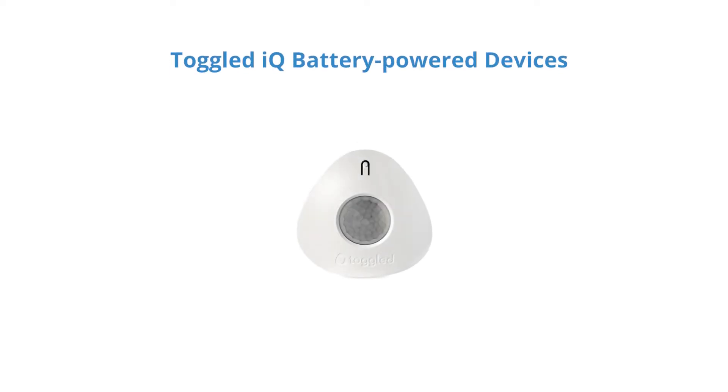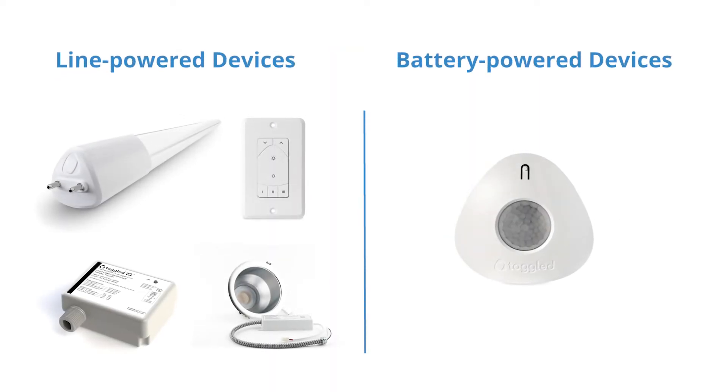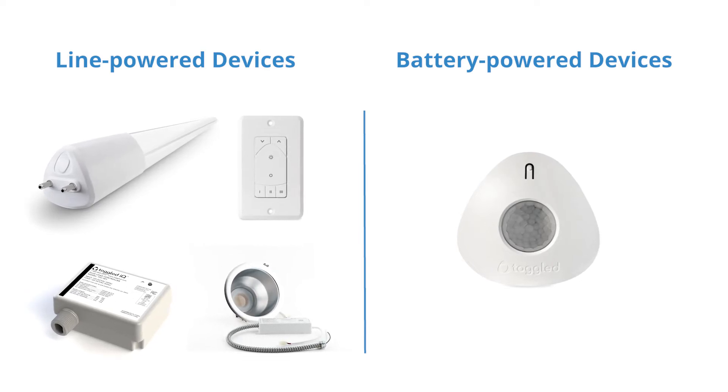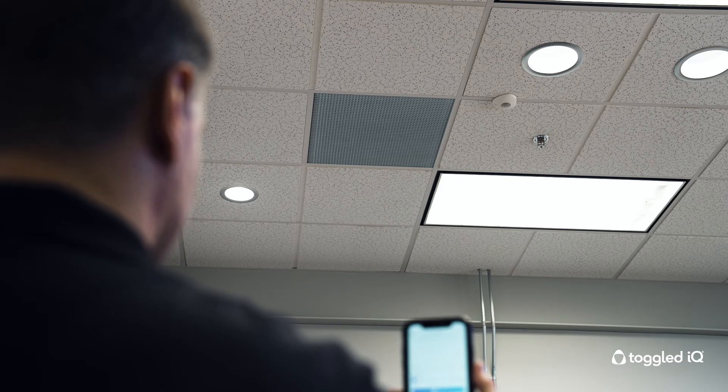Battery-powered Toggled iQ devices, such as the Toggled iQ sensor, do not act as repeaters or extend the range of your network. This is to conserve battery life. As a result, battery-powered devices must be installed within 30 feet or 9 meters of a line-powered Toggled iQ device. They also may not be leveraged as a connection point for your mobile device. To connect to your network, you must be within 30 feet of a commissioned, line-powered device. It's important to note your surroundings when commissioning, as they can have an effect on the Bluetooth range.